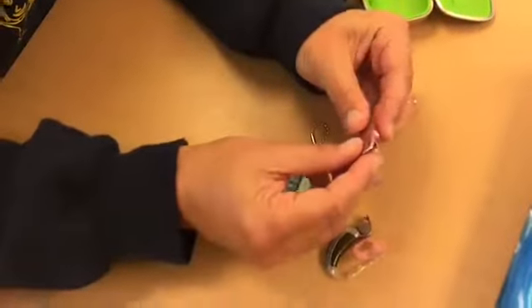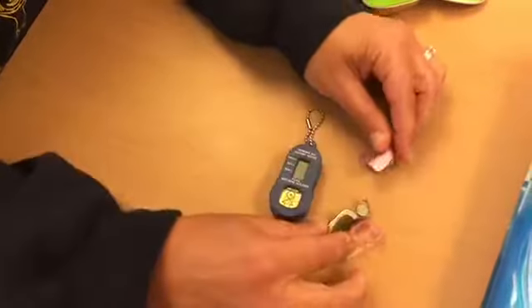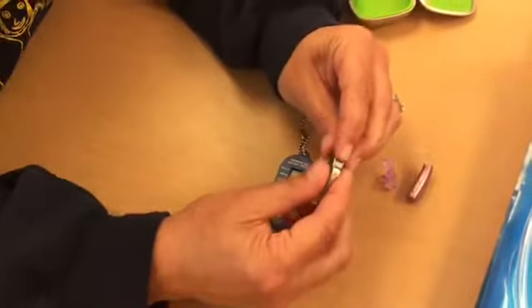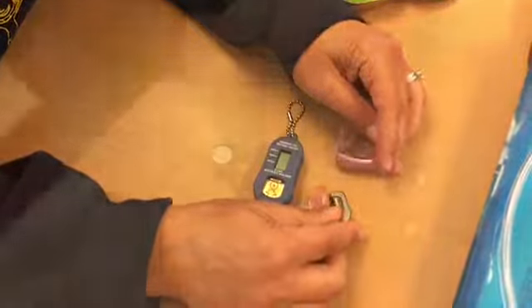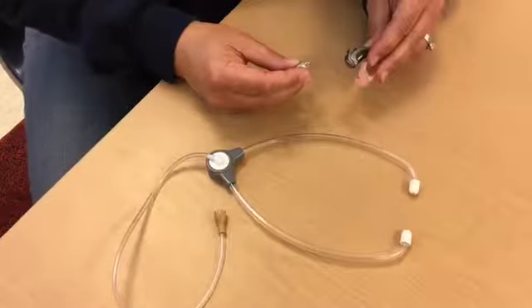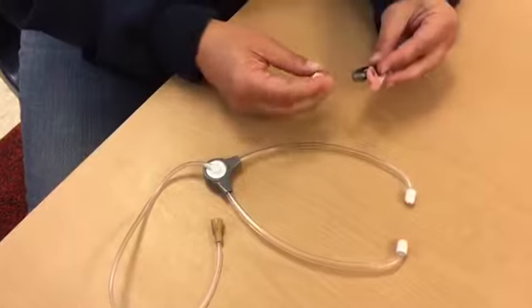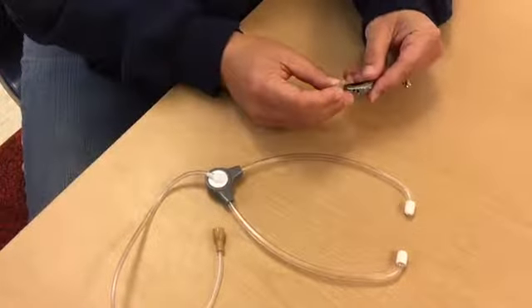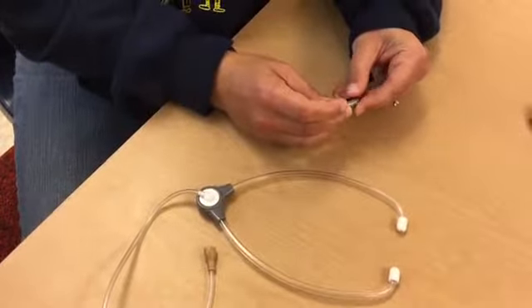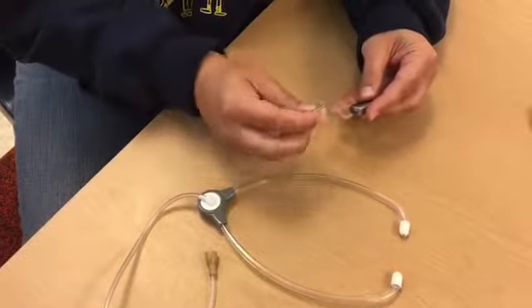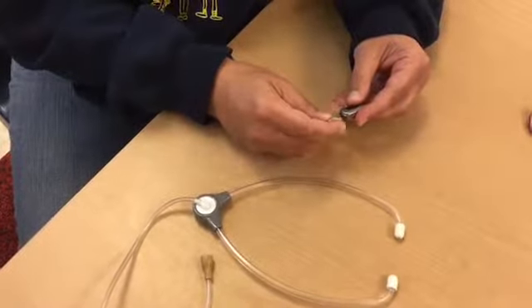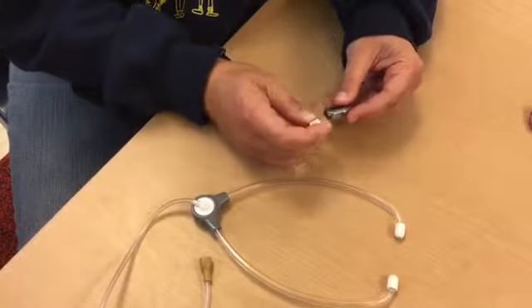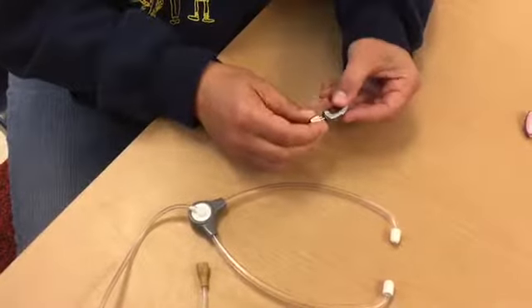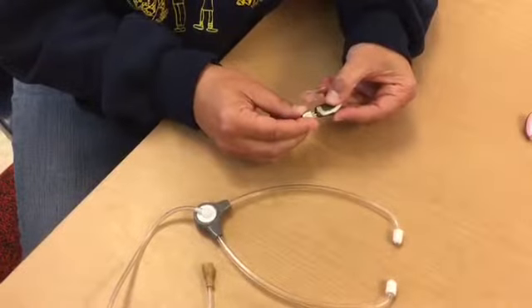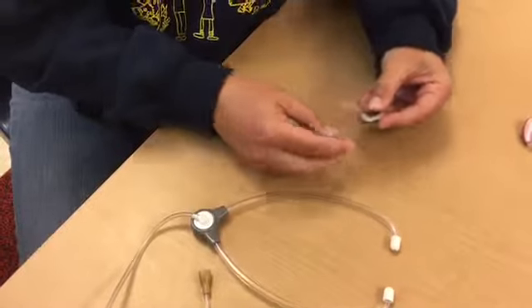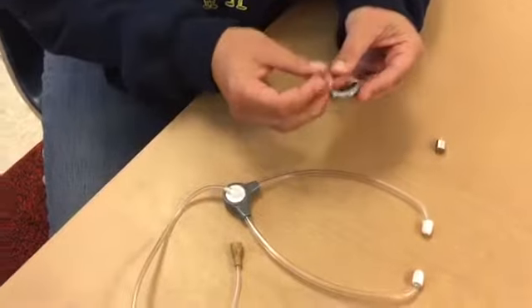So then when you're done checking the battery, you close the battery doors, and that activates the device so that you can do your sound check. So the last part is really to do a listening check to make sure that the device is working. So for the hearing aid, the student's battery door is going to close, and then the boot or the receiver is going to attach onto the bottom. This hearing aid doesn't fit on here, but the receiver will be attached to the bottom. So then you close the battery door, and you should be able to hear the device turn on.